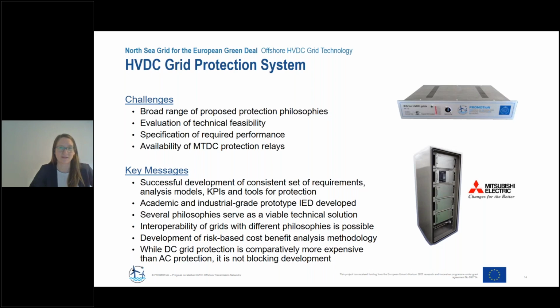The analysis found that several protection philosophies serve as viable technical solutions, and that different strategies could be used when different grids with different protection strategies are later interconnected, for example using a DC circuit breaker as a grid splitting element between different protection zones within the grid. To analyze not only the technical side but also the cost side, a risk-based cost-benefit analysis methodology was developed for future HVDC protection systems.